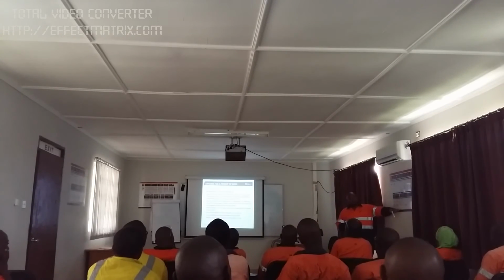So as we say, the last thing that an authorizer does is to authorize the job. So you can issue as many permits, but the authorization now depends on whether the requirements have been met. So, I was issuing you a safe work permit; before I authorized, we identified that you require a hot work permit and a confined space permit. Then, before I authorize you, I have to see what? Those permits attached.